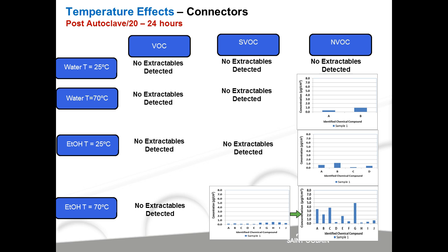So overall, we've found that the variability of our analytical equipment from injection to injection is quite low. The variability of our extraction method is very reproducible. There is a little bit of lot-to-lot variability, but generally it's small compared to variability we've seen in other things like the difference between autoclave and gamma radiation or lab-to-lab testing variability.